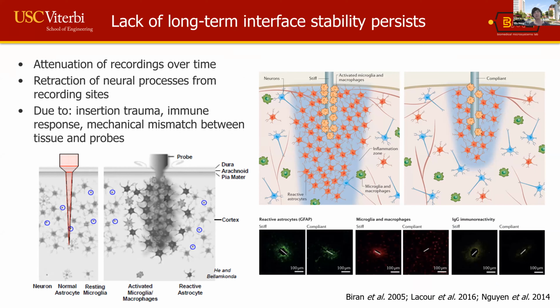And what I mean by that, to be specific, is that when you implant a device, typically you can get decent recordings for a short period of time. Over time, the presence of the implant will cause a scar to form, as well as a number of different activities that are undesirable. They all constitute an immune response. And what that can do is that, if you look at this cartoon down here, you want to have neurons in close proximity to the electrode. If a scar forms, or if there is just damage to neurons, you can cause neuronal death, or you can cause neurons to be pushed away from the electrodes. And so that can contribute to a degradation of recording quality over time.